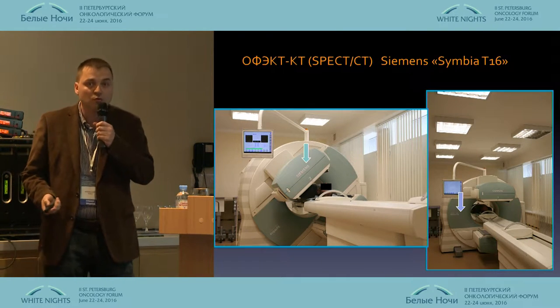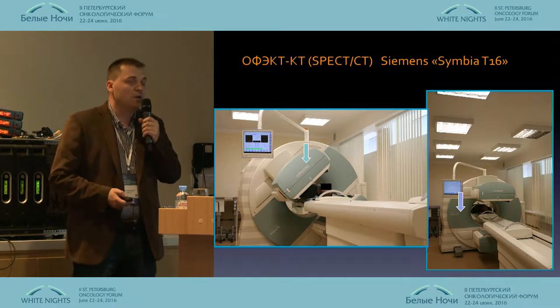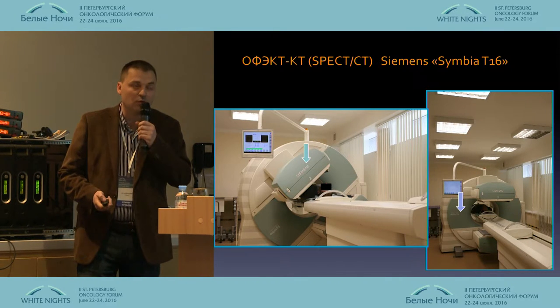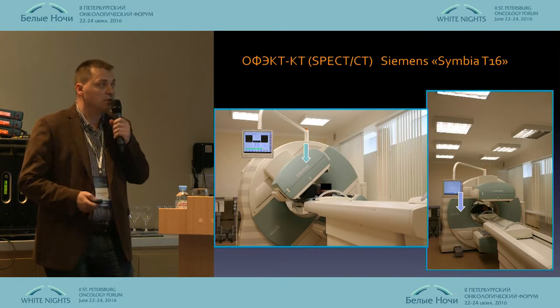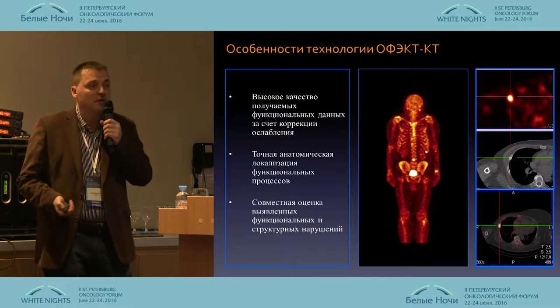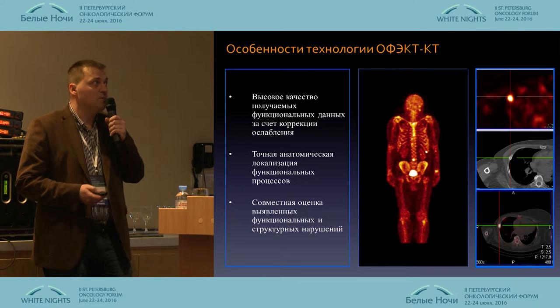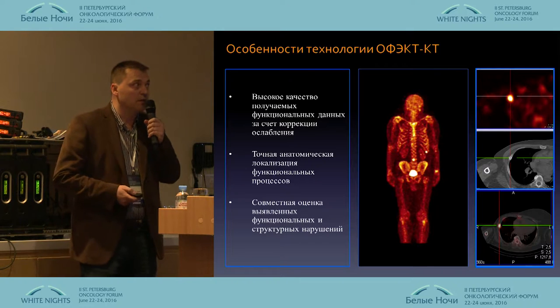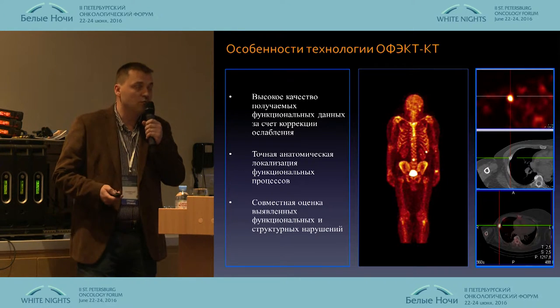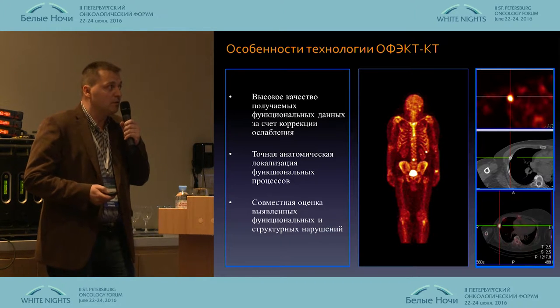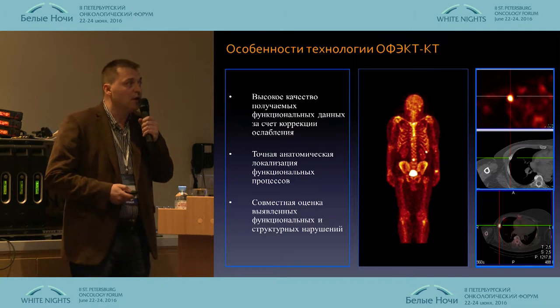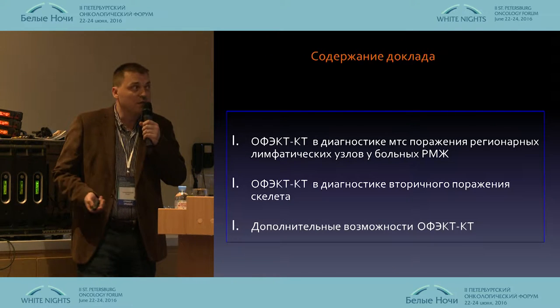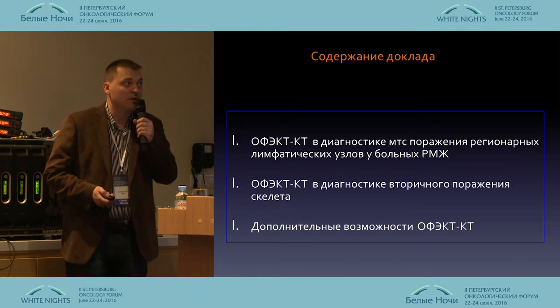SPECT/CT is a hybrid device which combines emission computer tomography and spiral X-ray computer tomography. This is a 16-slice tomographic machine. Its specifics are high quality of functional data, precise anatomic localization of functional processes, and joint assessment of functional and structural disorders.